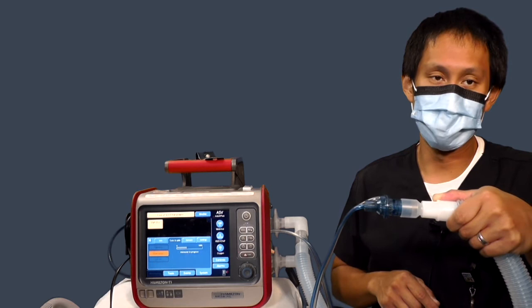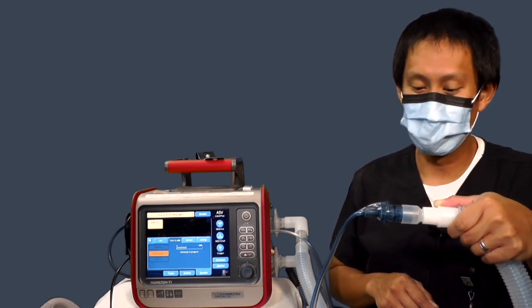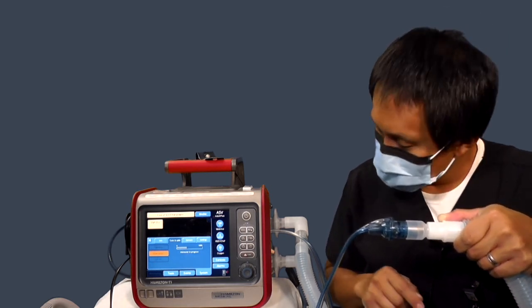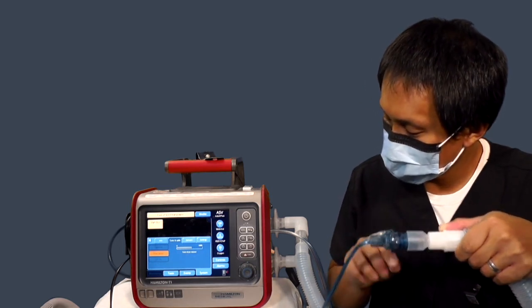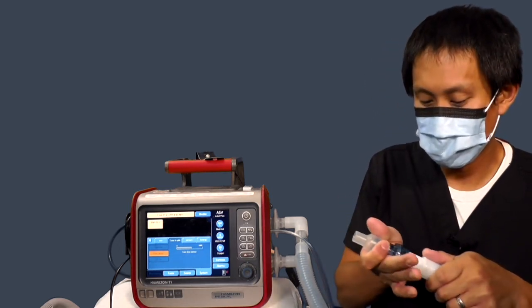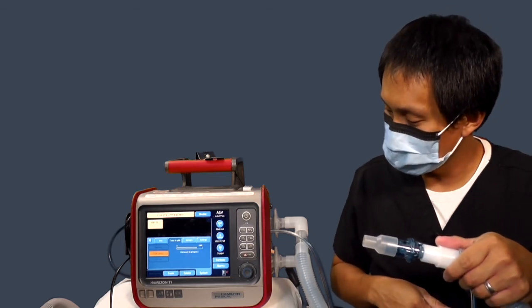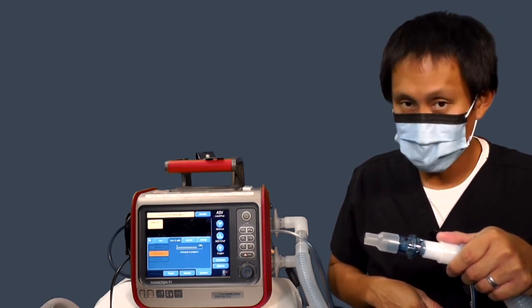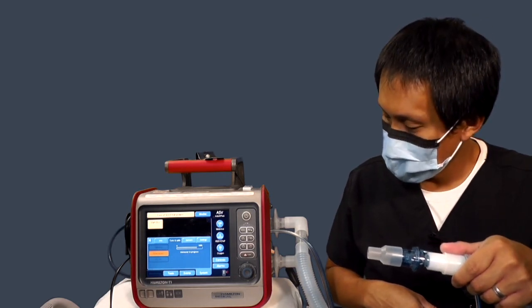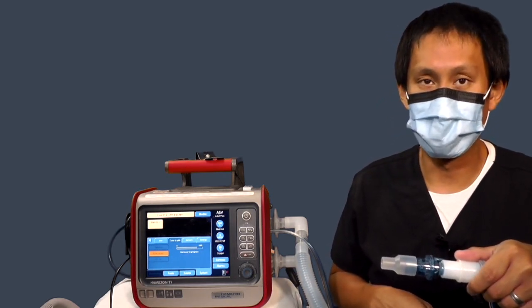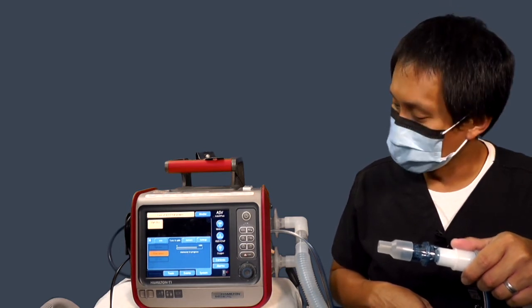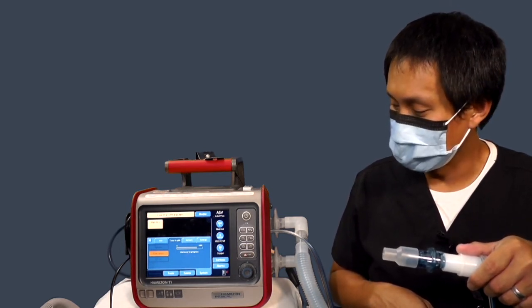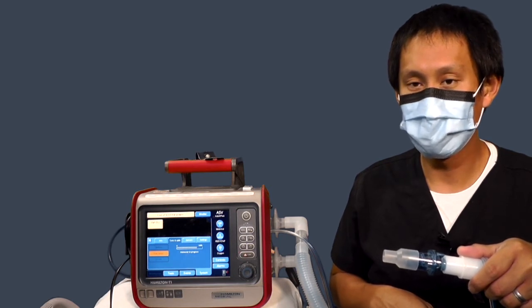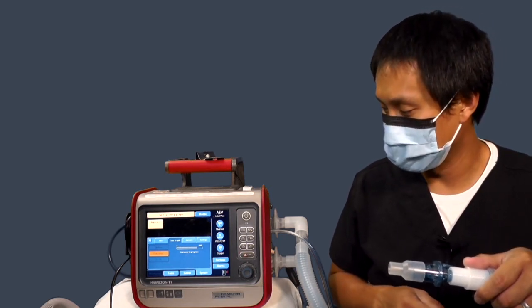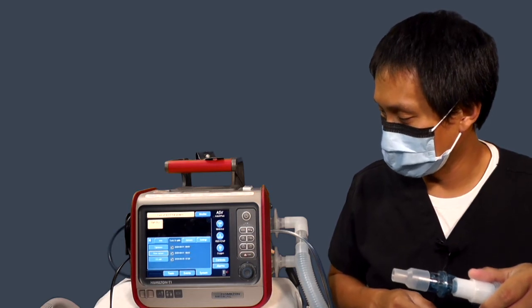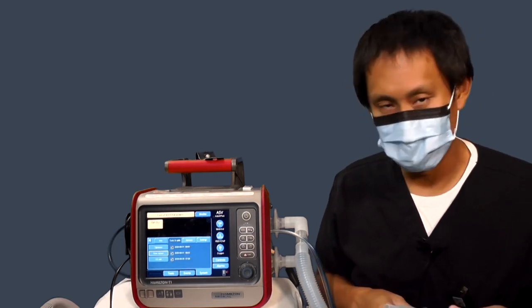As the flow sensor is going through the test, you'll notice it starts winding up louder and louder. Now it's wanting me to turn the flow sensor around. As long as you perform the prompts within a few seconds of the message coming on, it will continue with the test. If you fail, let's say you get distracted, when the message prompt changes, it will fail your test and you have to start all over again.